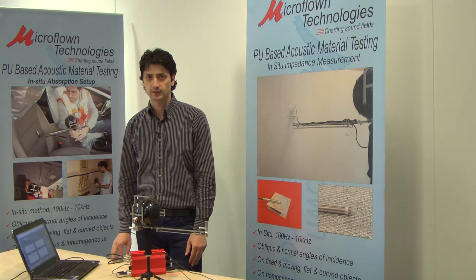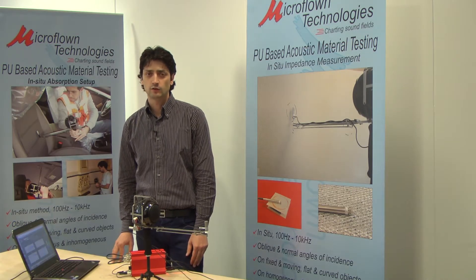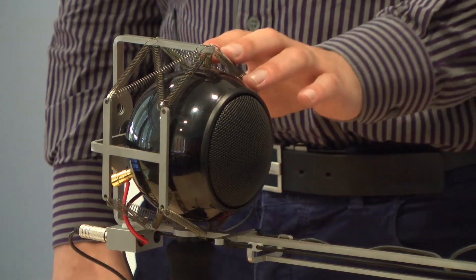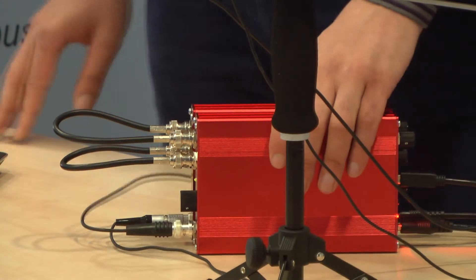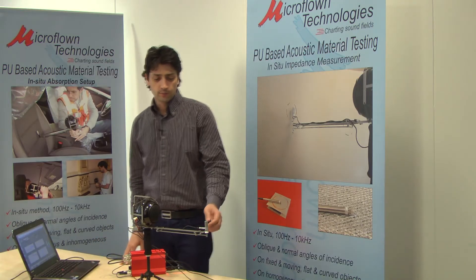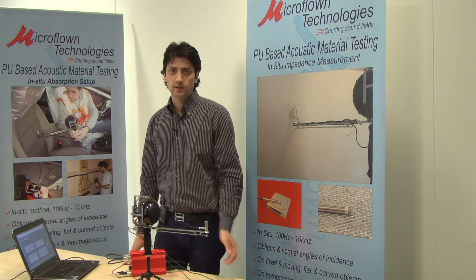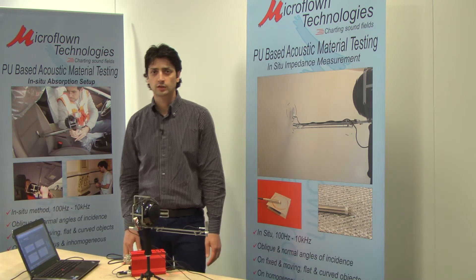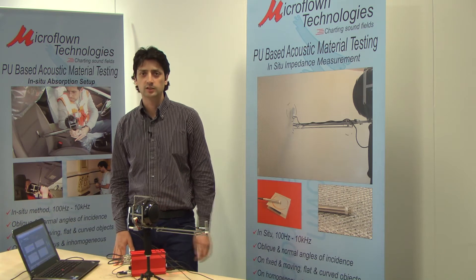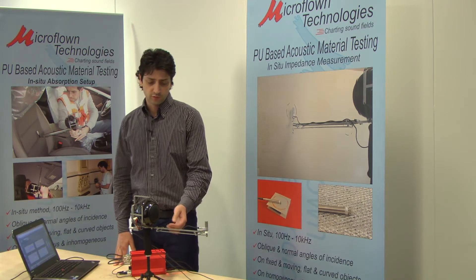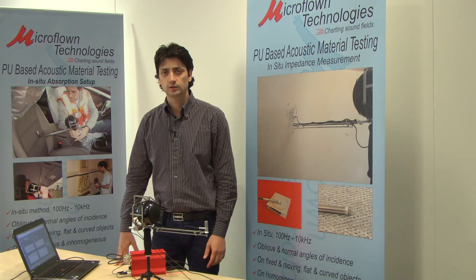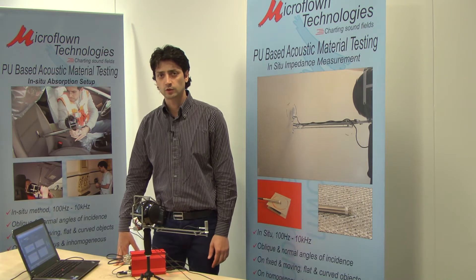The Microflown Acoustic Absorption Setup is a novel solution which includes a normal PU Mini, a loudspeaker, a two-channel signal conditioner and DAC, and a normal laptop. The PU Mini probe can measure both pressure and particle velocity close to the surface when noise is generated through a loudspeaker at a certain distance. The frame is used to decouple the probe from the loudspeaker and avoid direct transmission of vibration.